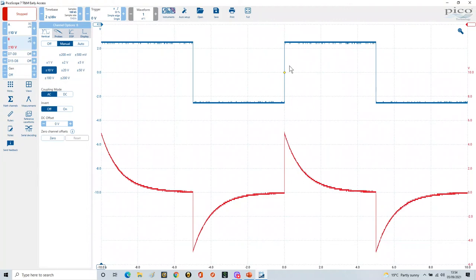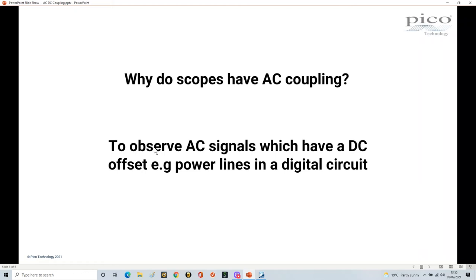What's important is you understand that what you're really seeing at the signal source is one thing, but this is what your oscilloscope is looking at. So what is the point of AC coupling? It's really to observe AC signals that have a DC offset — for example, power lines on a digital circuit. It's a great way of finding out what elements might be causing trouble when you look at the noise that's actually on a power line, and the way you do that is by using AC coupling.